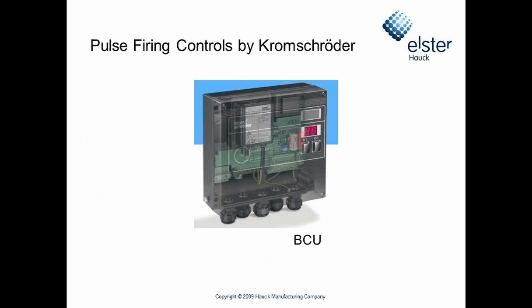If you prefer local flame supervision, we have the Kromschroder BCU. Again, the flame relay is designed to take the high duty cycle. The BCUs have built-in outputs for the gas valves and the air valves. So you provide a go signal, and it will cycle the air and gas valves as needed.